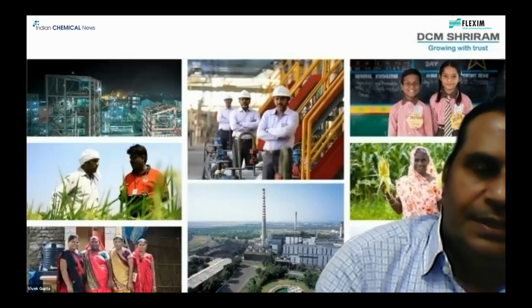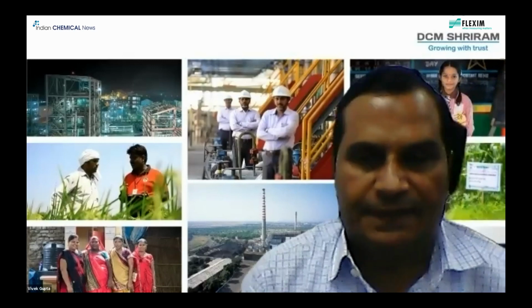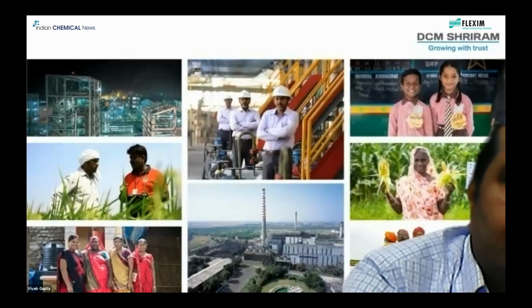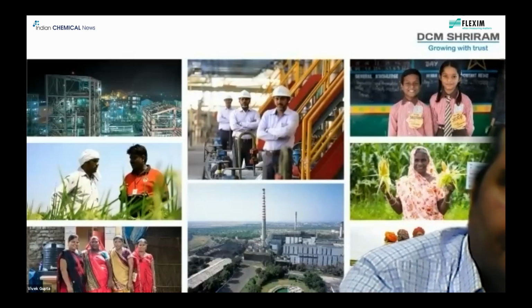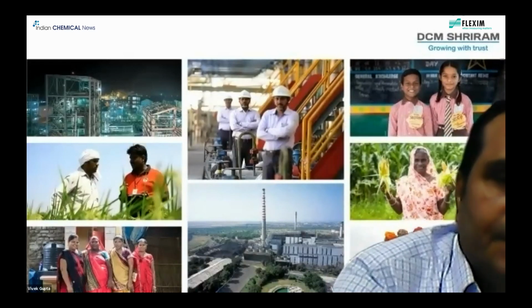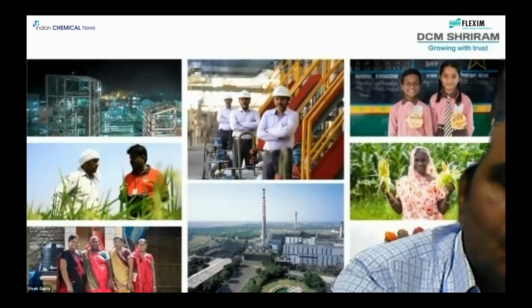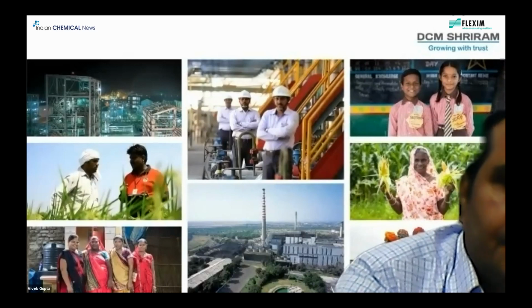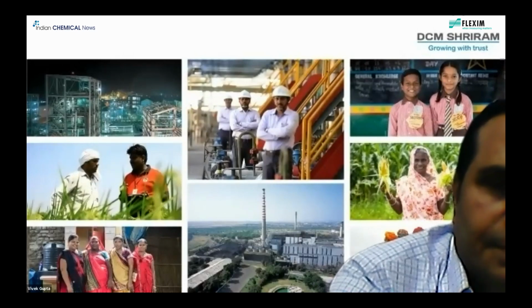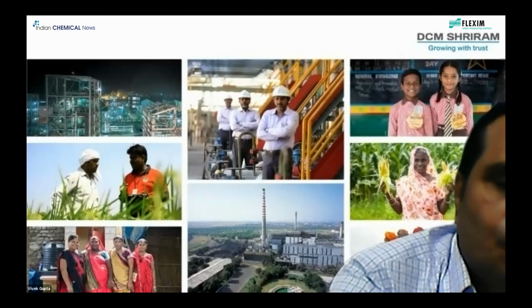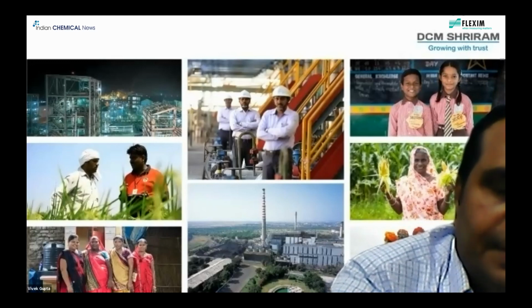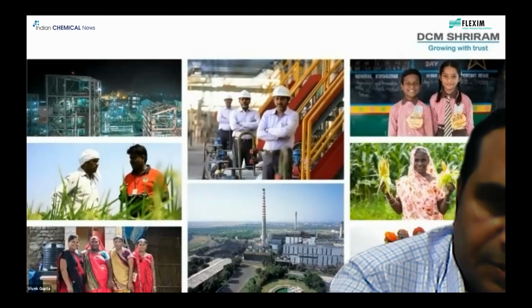And number three is the preventive maintenance of these instruments, because some of them, like I was telling you, in the clamp on flow meter, there is a signal strength. If the signal strength has gone below 60 dB, it means there is something wrong with the sensor. So that needs to be checked, and that is what I was telling you in my previous answers, that there were some complaints, and then we found that the signal strength had gone below 60 dB.